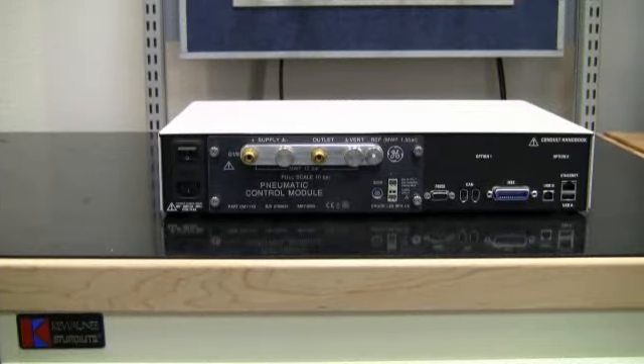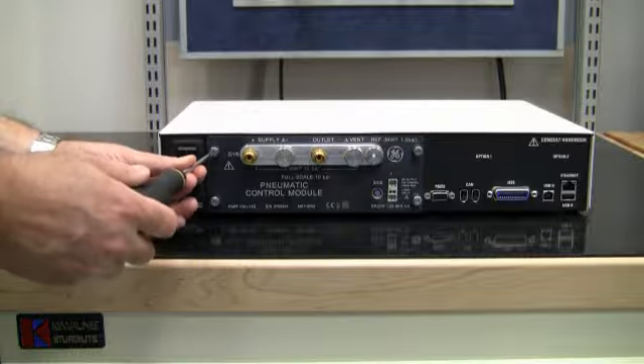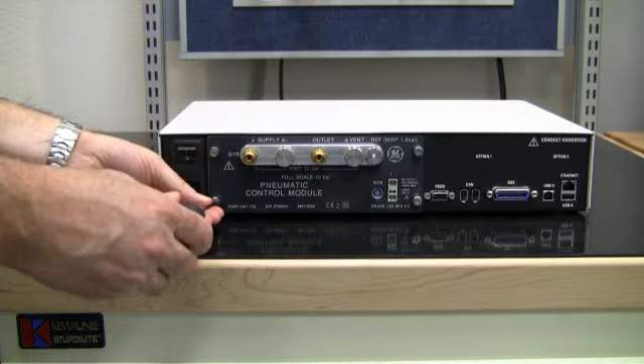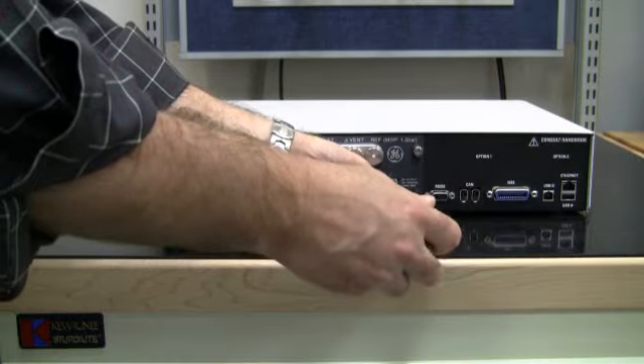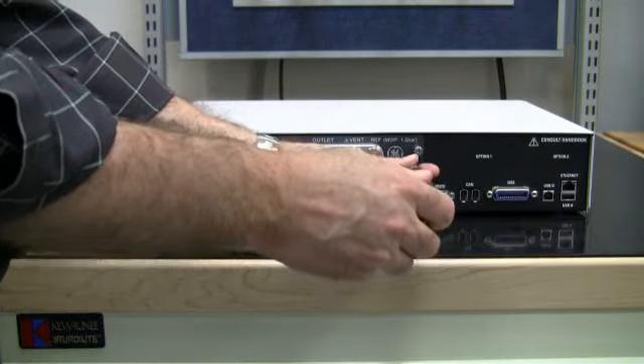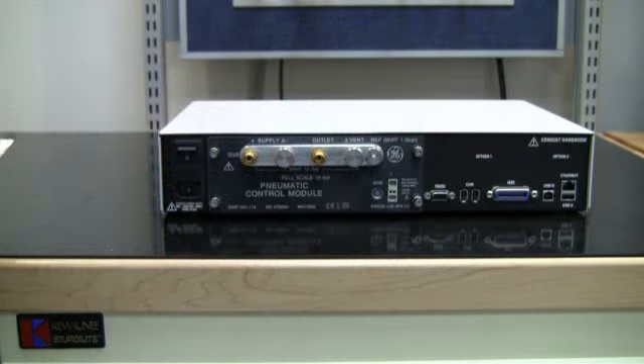As mentioned previously, PACE5000 is designed on a highly modular platform. The control module can be easily removed to change pressure ranges or replaced with the same range when it is time for recalibration. It also simplifies the process when PACE5000 is mounted in a rack or cabinet-based system. To remove the module, first switch the power supply switch to the off position and unplug the power cord. All pneumatic lines should be vented and disconnected. Then, unscrew the 4 retaining screws and slide the module out of the chassis.